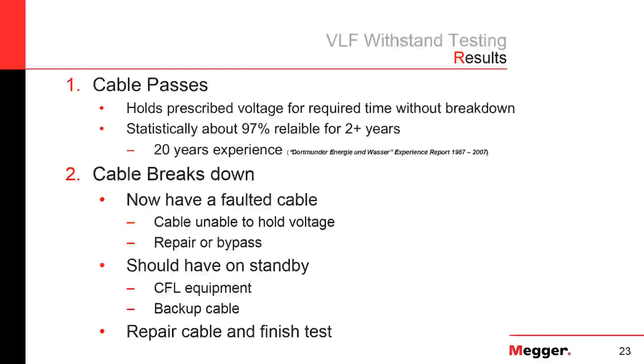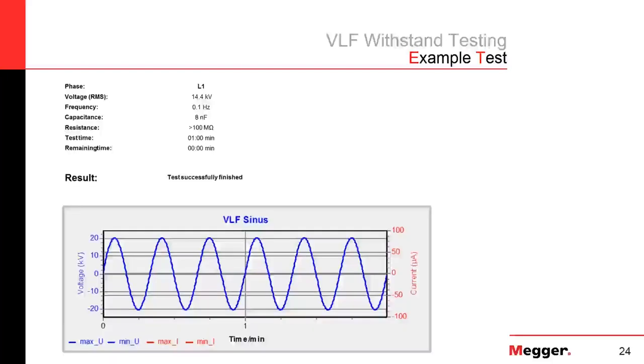If the cable does fail, we go out, repair the cable, and continue the test. We don't need to restart the test. If the cable failed 15 minutes in, we repair the cable, start the test back up, and hold the voltage on there for 45 more minutes. We don't need to restart from zero.